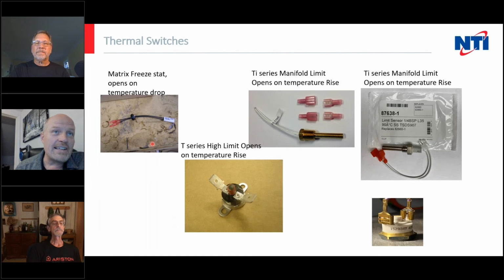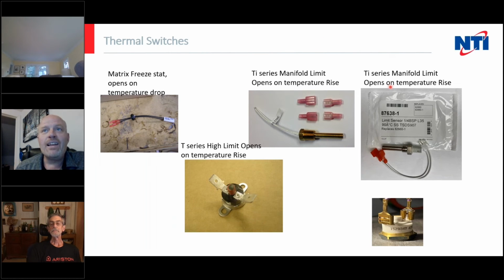The Matrix Freeze Stat is a bimetal strip, except it's one that's designed to read cold rather than hot. T-Series safety limit, these were a snap disc and manual reset. TI Series manifold high limit. The TI Series, that actually should say stack limit, but anyways, that would be a stack limit there. And the only place we use it on the new boilers is on the burner door.